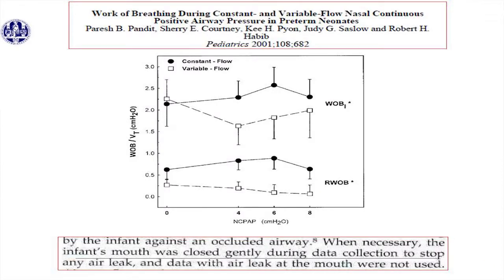Then in infants, Courtney did this work of breathing study, which is often quoted. And she compared constant flow with variable flow. And this is the variable flow work of breathing, and this is the constant flow. You can see there's a difference. There's less work of breathing if you use the variable flow, and she used the infant flow driver. But if you read the methods more carefully, they say, when necessary, the infant's mouth was closed gently during data collection to stop any air leak, and data with air leak at the mouth were not used. So this only tells you that the fluidic flip or the lower work of breathing only works when there is no leak.